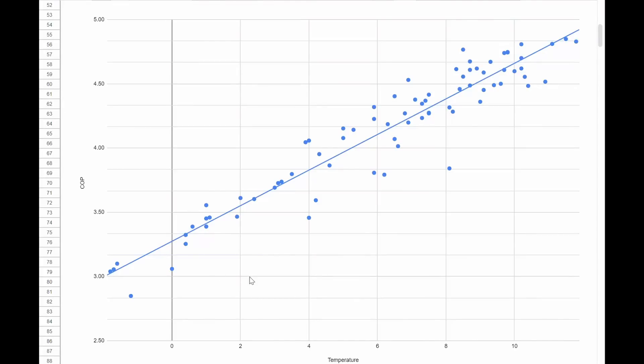I've been plotting all the information into this scatter graph. Along the bottom is the average daily outdoor temperature, and up the left-hand side is the average daily COP. You can see where the trend line is. Roughly, to achieve a COP of 4, we're looking at about 5 degrees Celsius outside. For a COP of 4.5, around 8.5 to 9 degrees outside. And heading for a COP of 5 looks like it would be about 12 degrees outside. I'll keep updating this scatter chart and including it in my monthly updates.